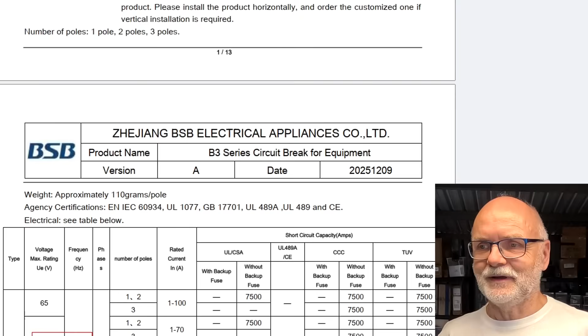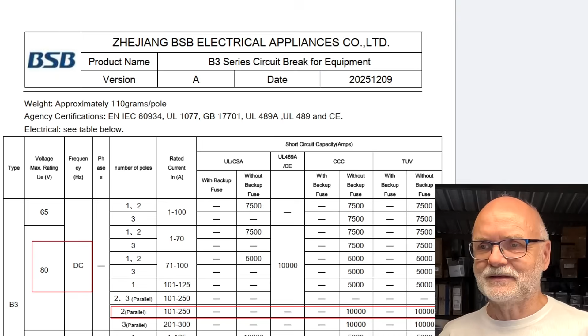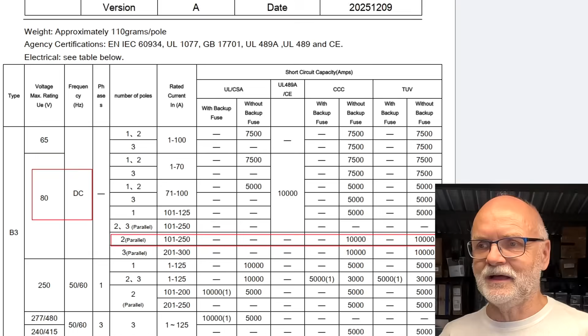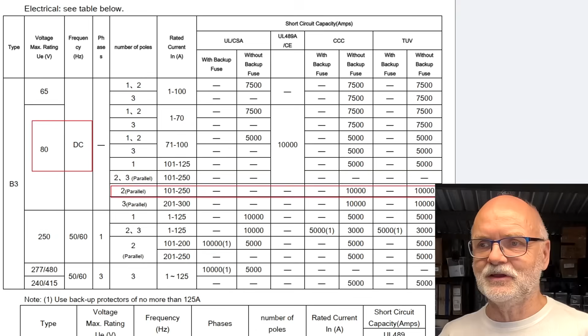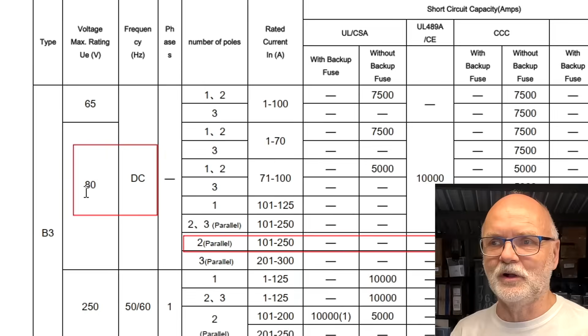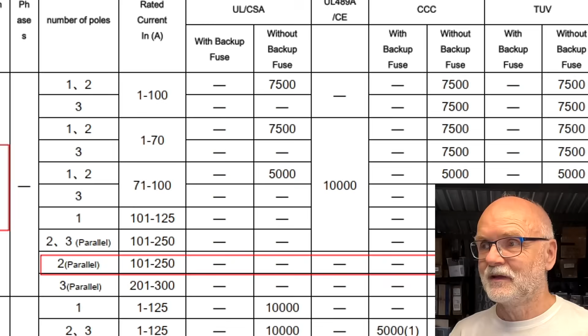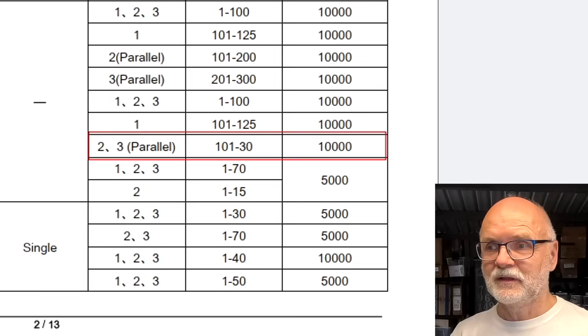All right, and down here, in the red boxes, this is the 80 volt rated DC circuit breaker. We've got two of them in parallel, yeah? This is one unit. It is not like we have two separate circuit breakers in parallel. It is one unit, and it is also connected mechanically at the front. So if one side trips, it flips the other side as well. Current ratings available for these two-parallel models are 101 to 250 amps. It says here again, 10 kiloamps of interruption current.